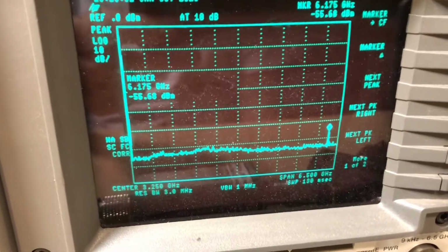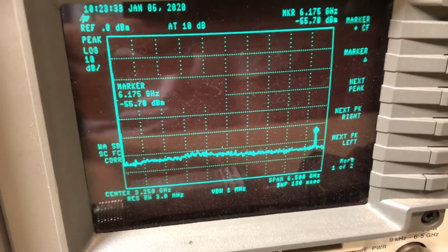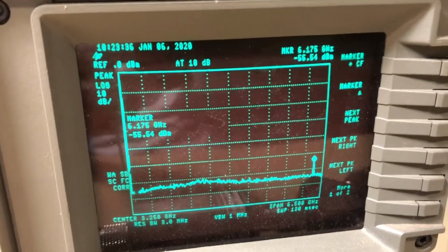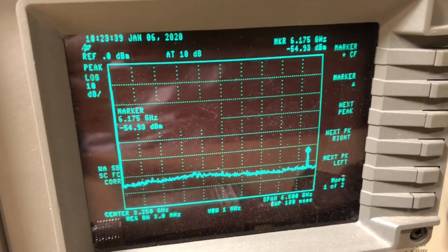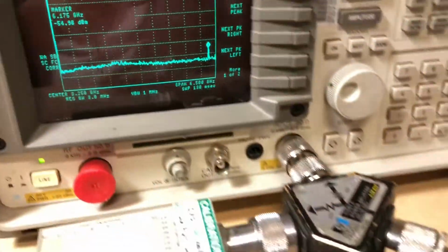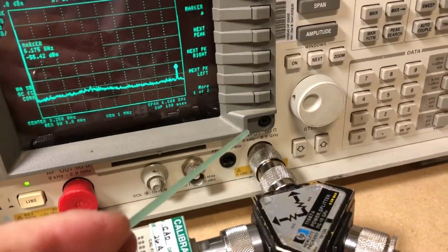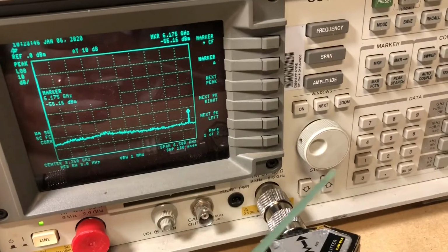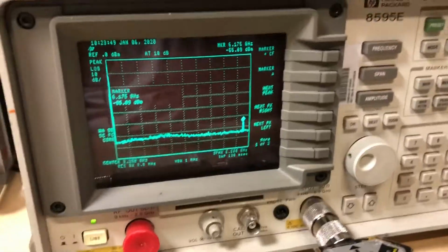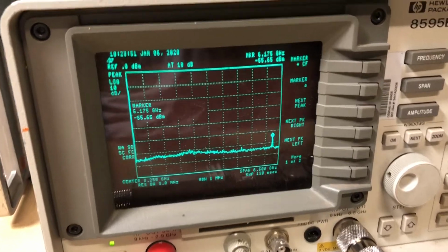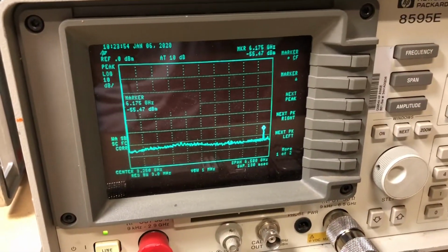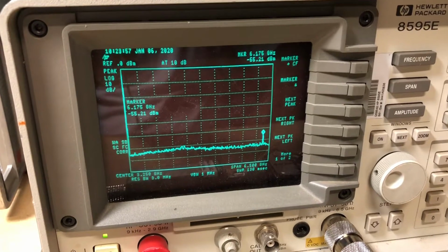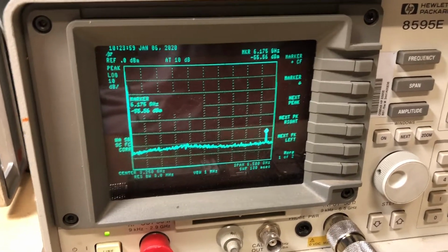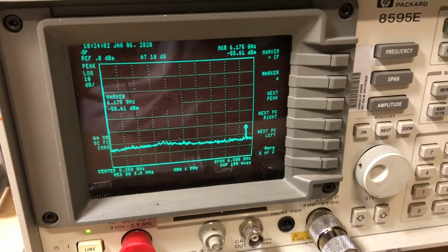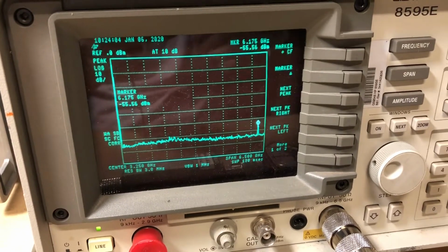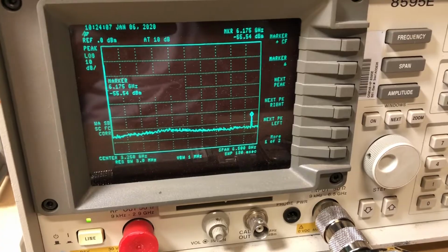So what I suspect is that there is a problem somewhere in the signal path from the RF input on the high band signal path that just goes into the input to the IF. I don't think there's a problem with the IF section just yet, and I will show you what I mean here in a minute. We'll get some drawings out and we'll look at the block diagram of the analyzer, because the unit seems to work just fine on the low band. The problem seems to be isolated to the high band.